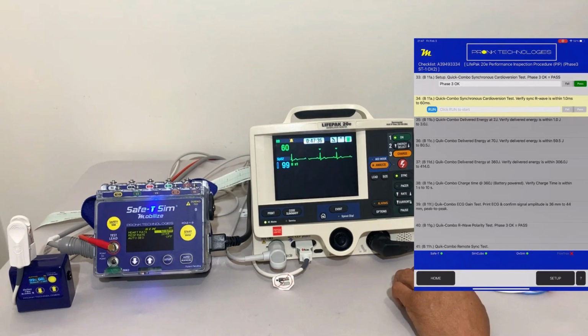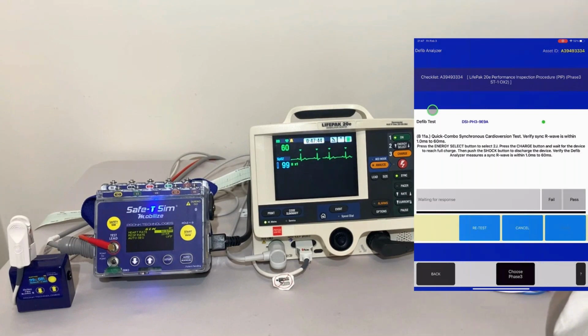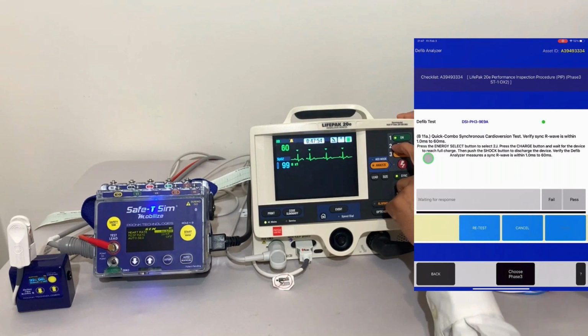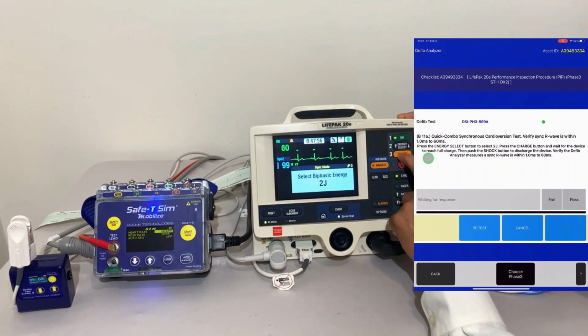Next we're going to do the synchronous cardioversion test, verifying the R wave is synced within a particular time. We run that test. We're going to utilize the phase 3 defibrillator analyzer for this test. We're going to verify that the timing is within 1 to 60 milliseconds. This requires us to charge the defibrillator to 2 joules, and we're set to that. We're going to charge it. We're going to fire the defib.